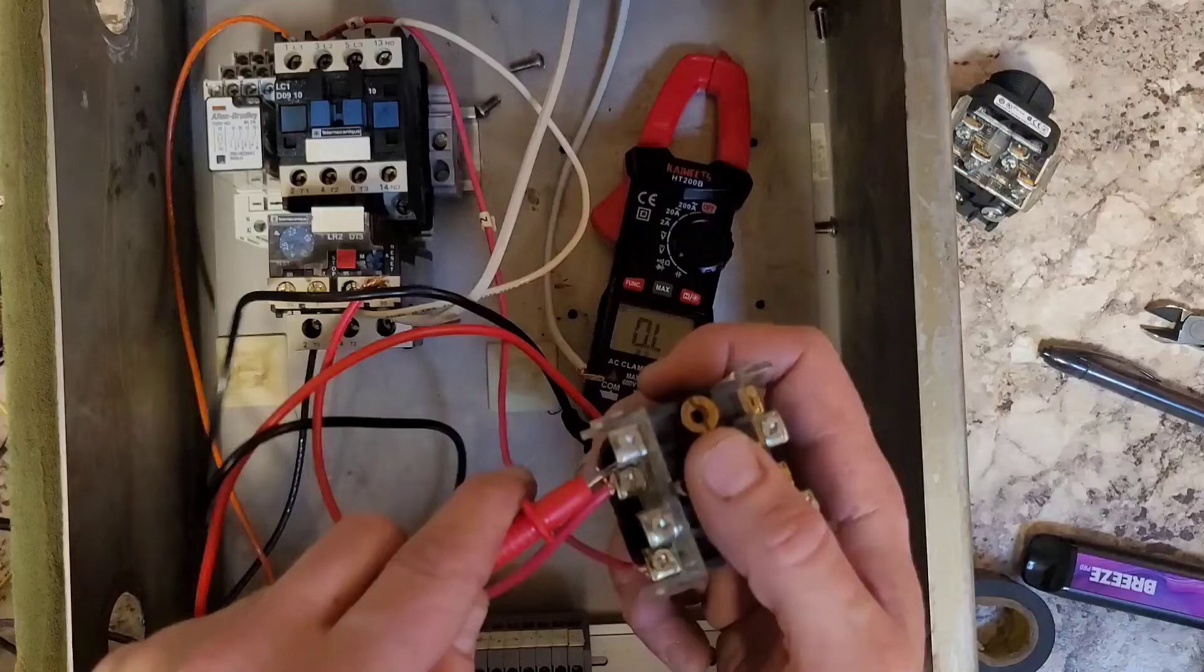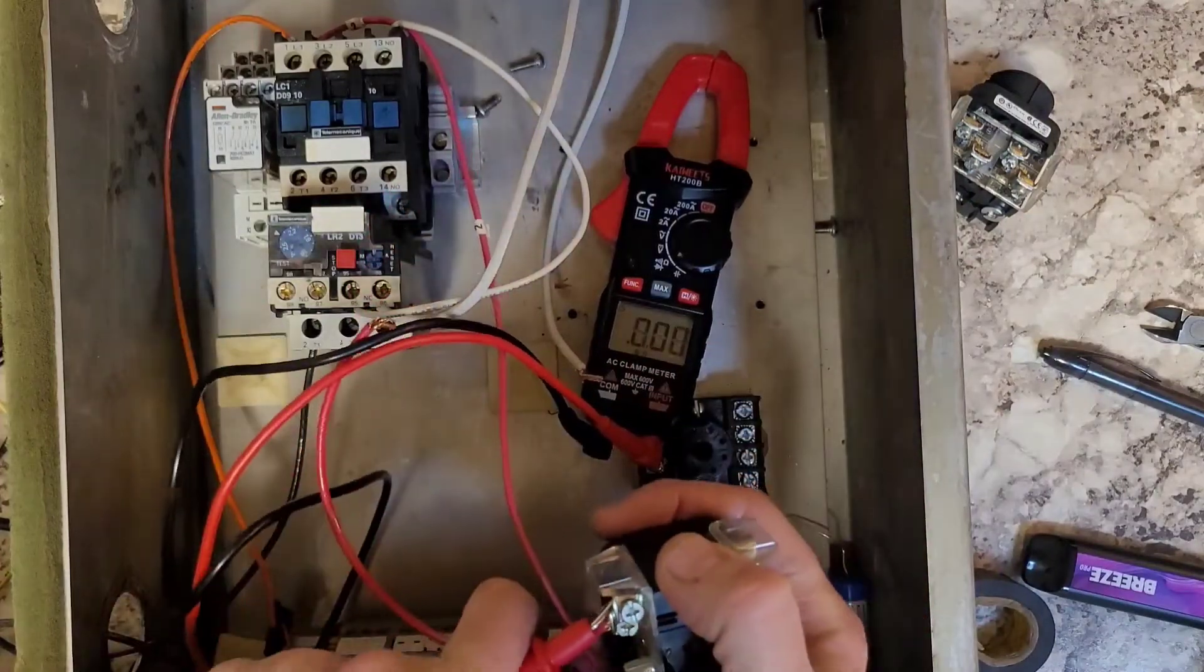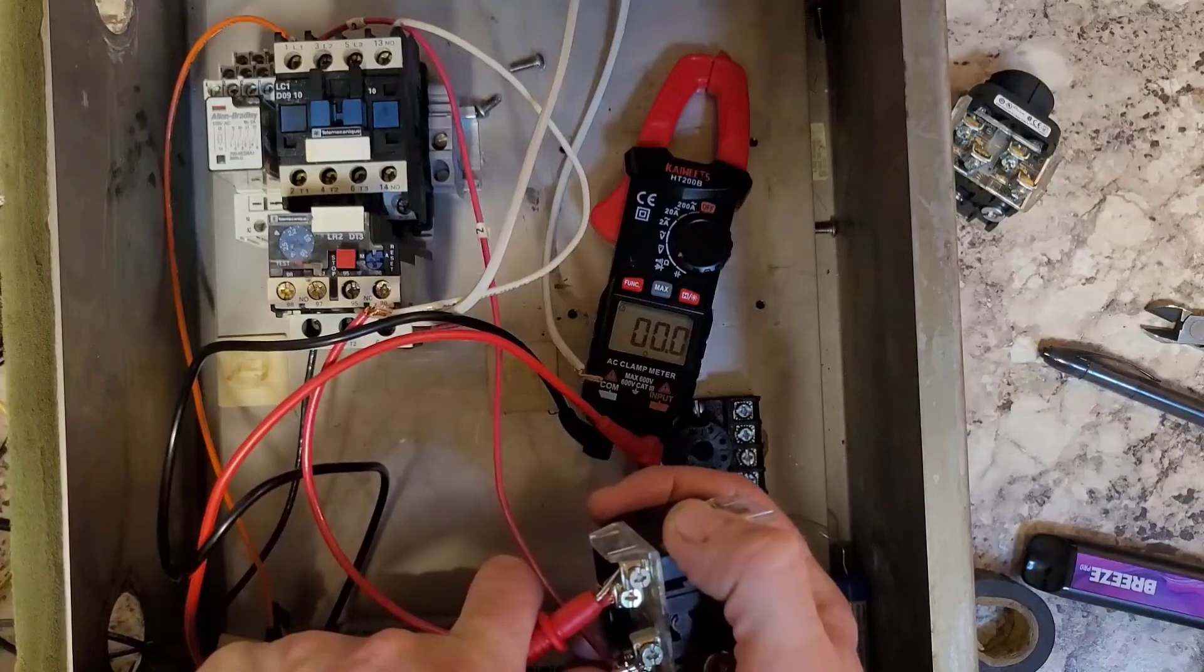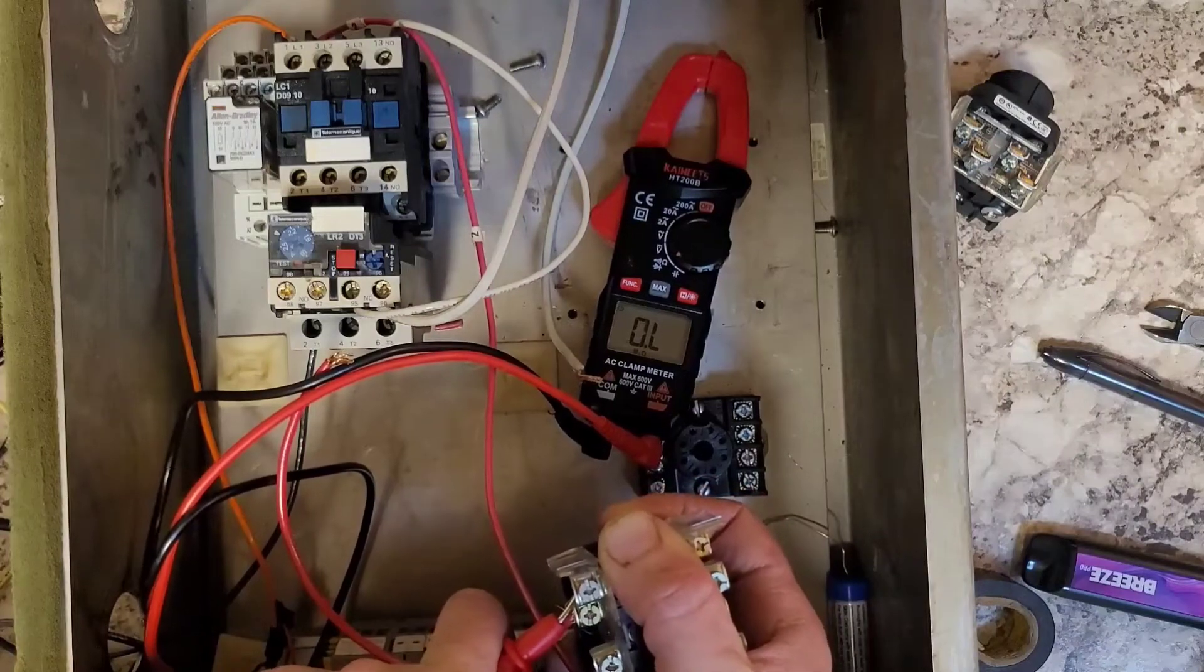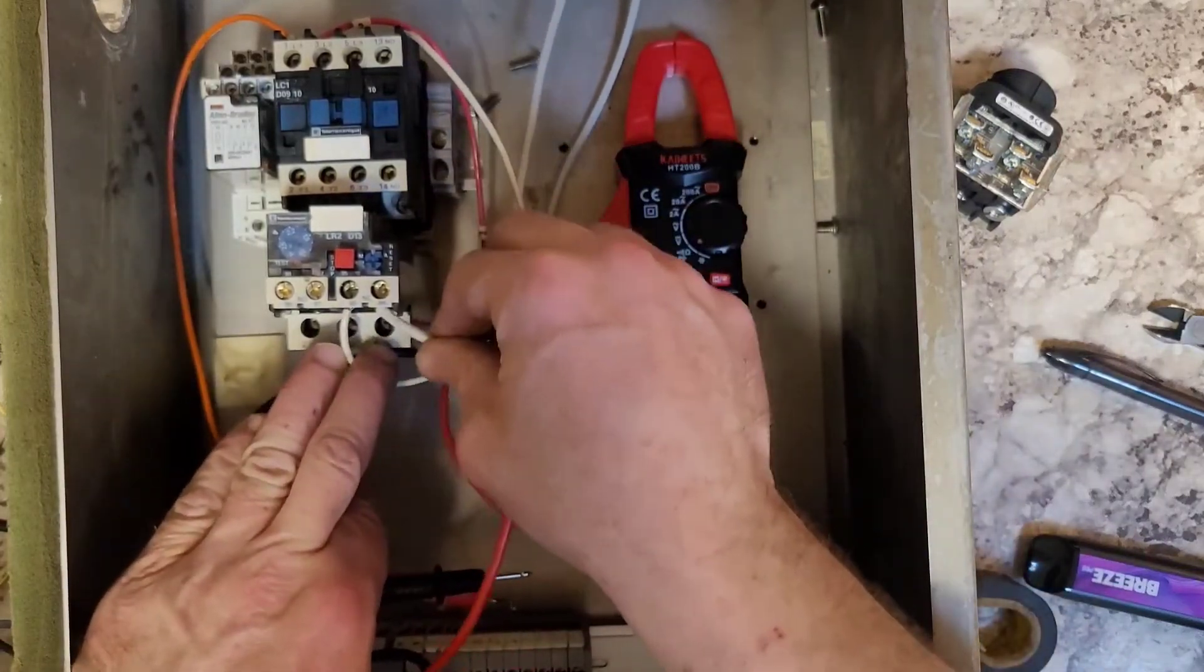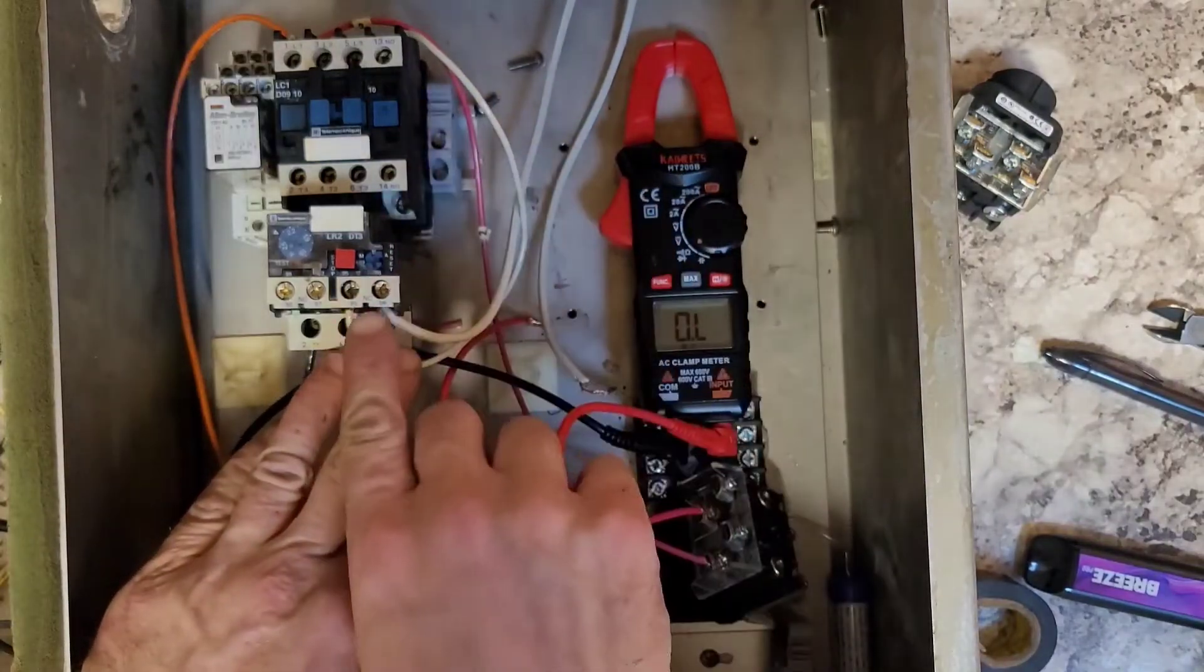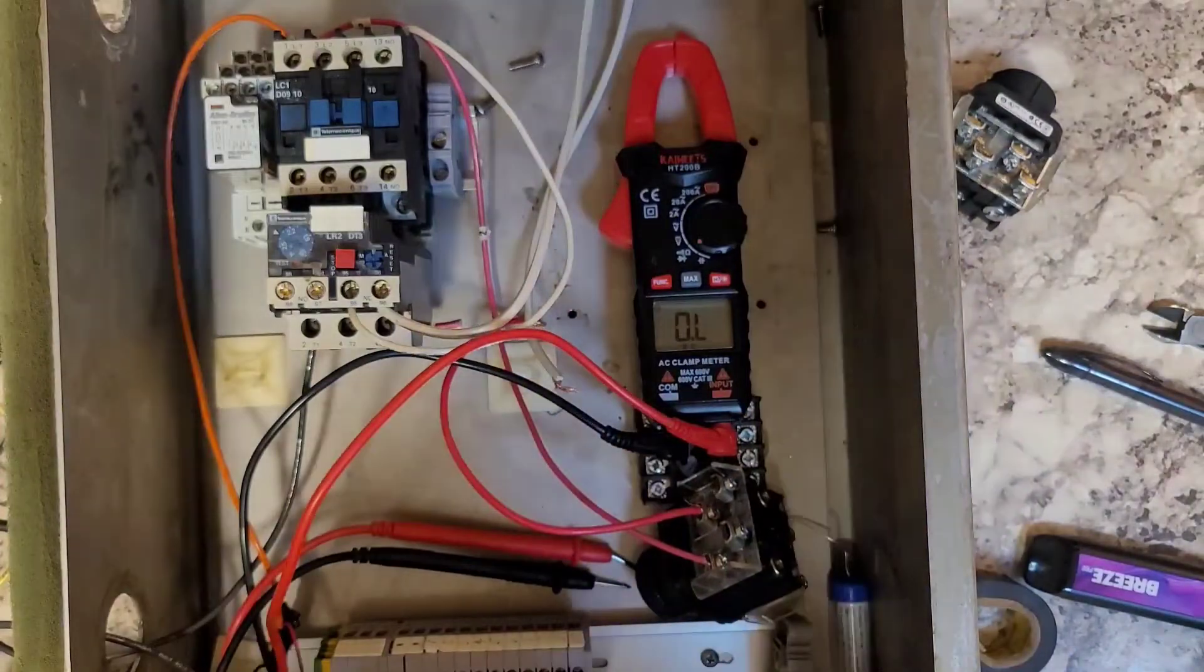This one here I already know - that's a closed circuit, you can see the ohms reading. Push that and it opens up, so that'll be our stop. Then like I discussed, this is our overload. When this says 'you're too high of current,' it will open up this normally closed set of contacts right there.